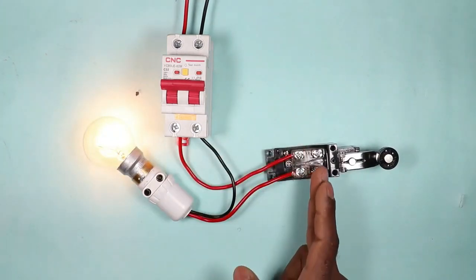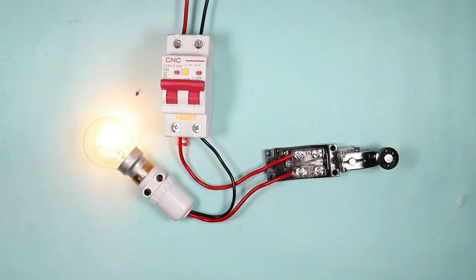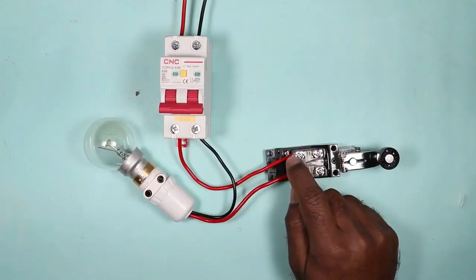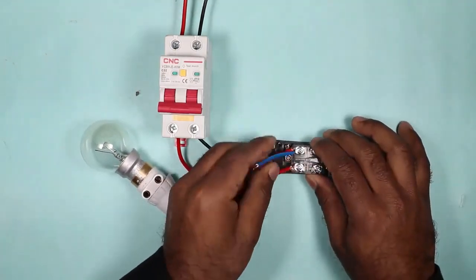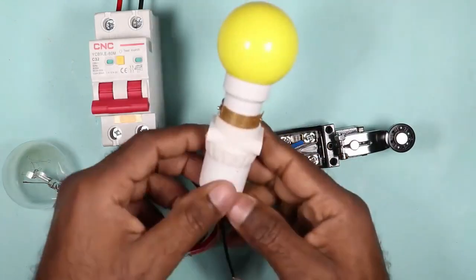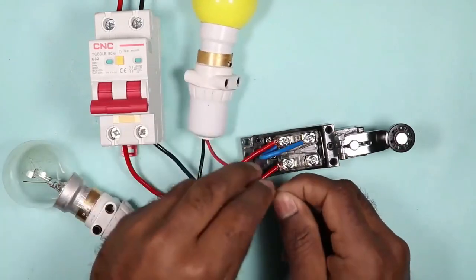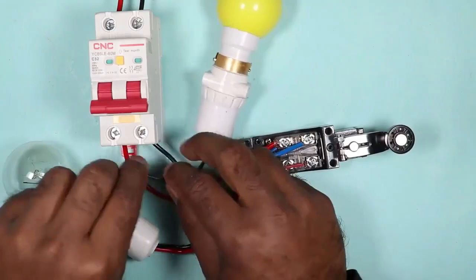Till now I explained about NO and NC contact. If you want to use both the contacts together, NO as well as NC, the phase supply wire to NC is to be looped with NO contact. So I am using a wire to supply power. To show the output signal from NO contact, I am connecting one more lamp. Phase wire is to be connected with NO contact and we will directly provide the neutral power supply.